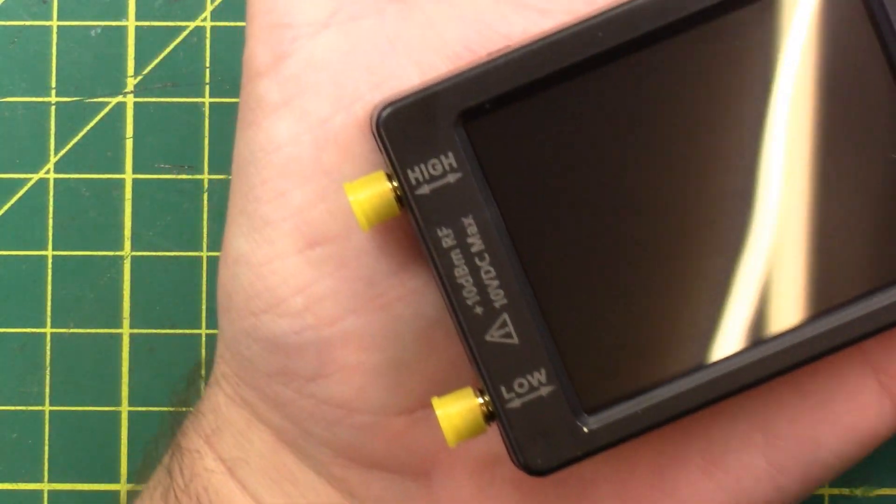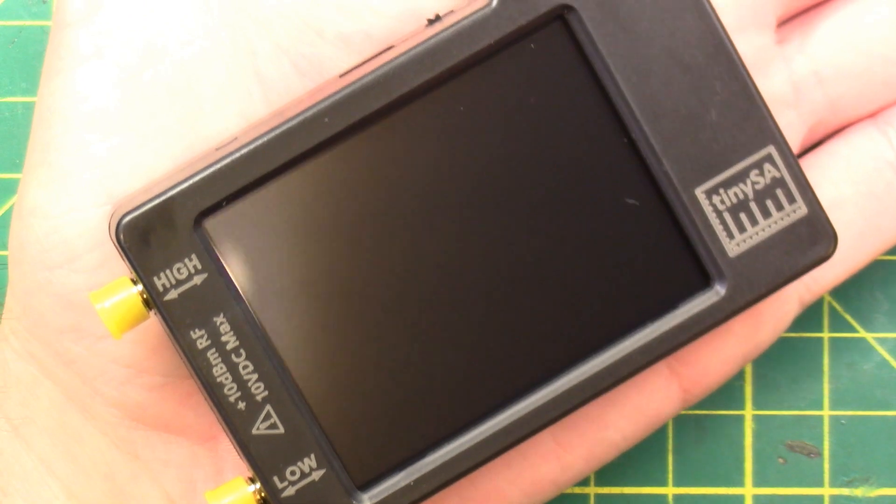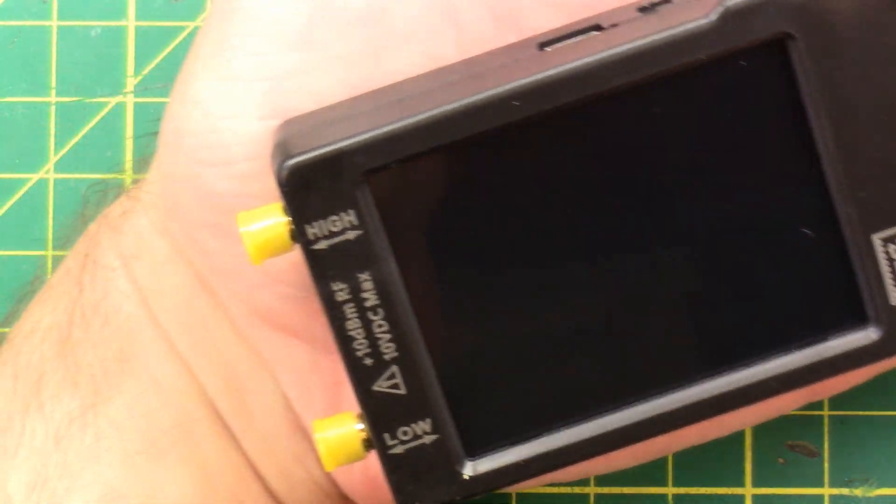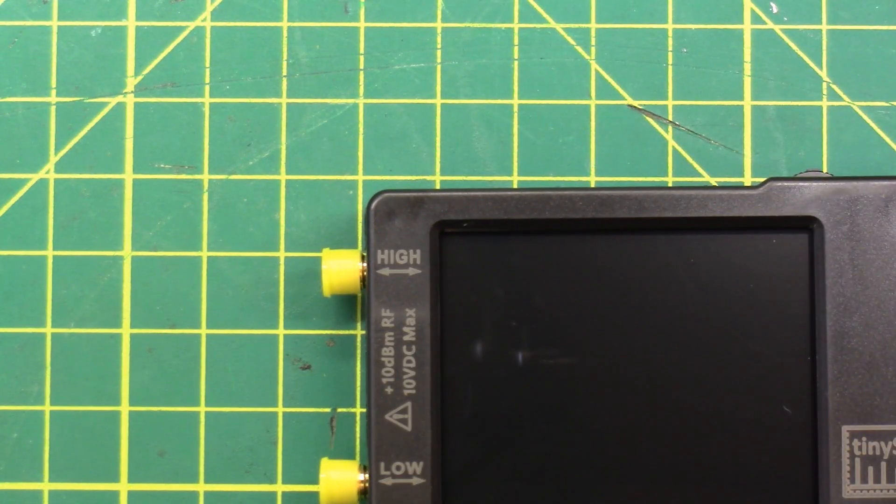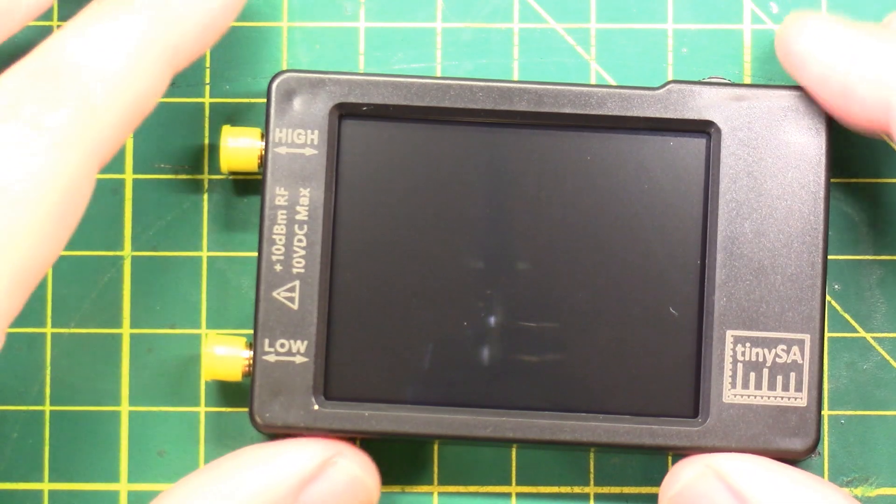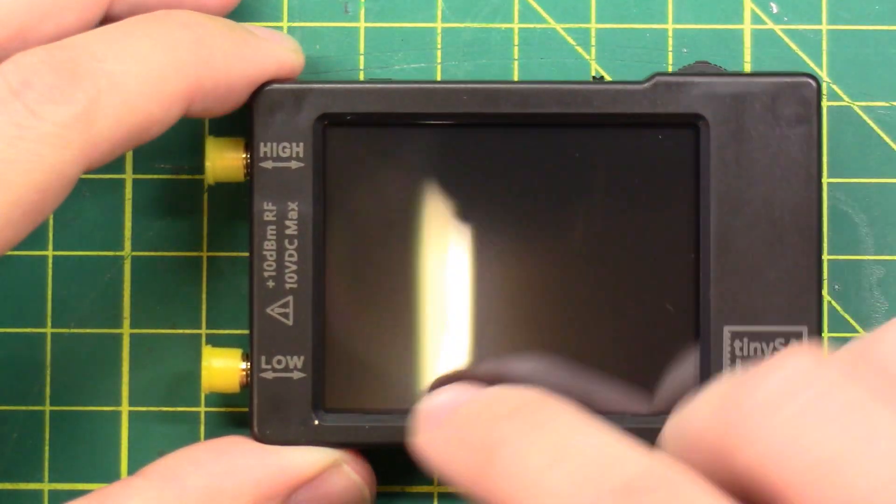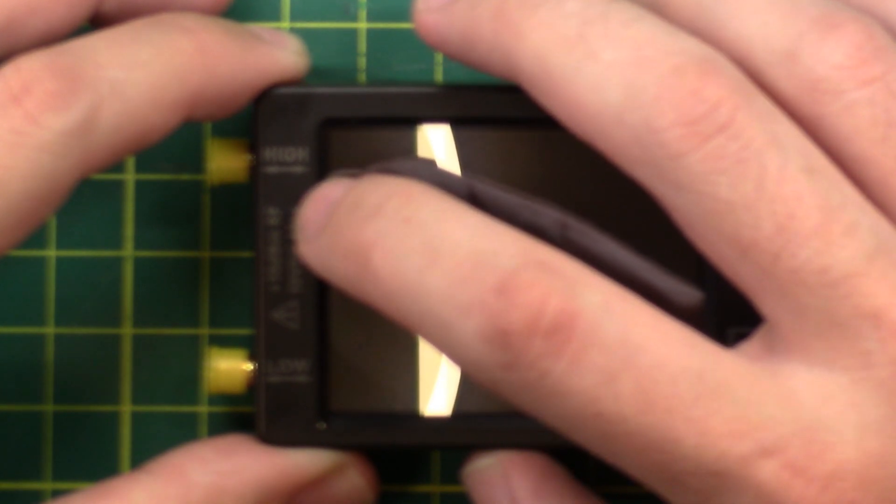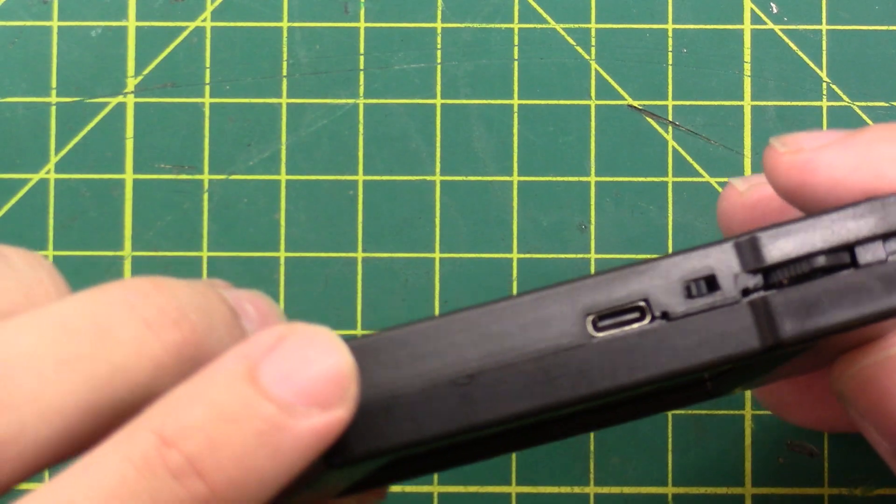The tiny SA fits in the palm of your hand. So now you can analyze all the spectrums in the palm of your hand. On the front side, you have a high port, a low port. It says plus 10 dBm, RF, 10 volts DC max. So don't overload your spectrum analyzers, folks.